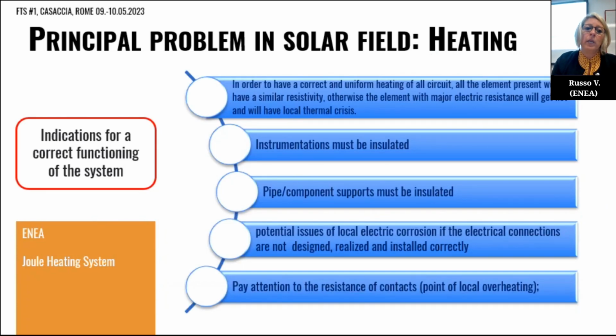Here are some indications for correct functioning of the system. First of all, in order to have a correct and uniform heating of the whole circuit, all the elements of the circuit should have similar resistivity. Otherwise, the element with the greater resistance will get hot and there will be possible overheating. Then all the instrumentation, all the pipe and component supports must be electrically insulated. And then we have to consider that it is possible to have a potential issue of local electric corrosion if the electrical connections are not designed and realized correctly. And finally, we have to pay attention to the contact resistance, because at this point we can have local overheating.